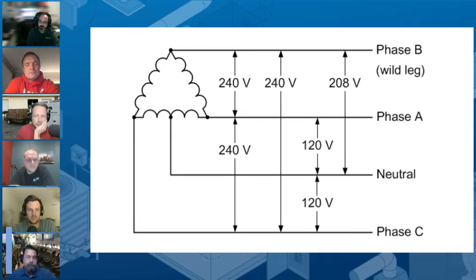When we were talking about testing across contact points — two really good things that have been brought up: use of an infrared camera is really handy for a lot of problems you'll find, and it matters more in three phase because single phasing and phase imbalance matters more. Motors running hot, poor connections — all that. The idea of measuring voltage drop across any connection or contact point, with the device energized and under load, is really valuable. If you go across the other legs and it's next to nothing but this one is 0.3 or 0.5 volts, grab your thermal imager and confirm it's hot. That's an indication you have a problem.